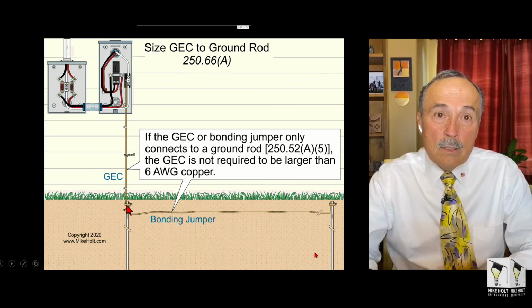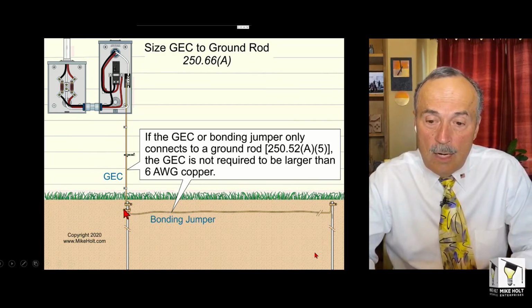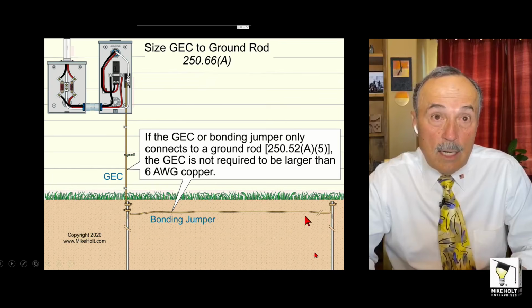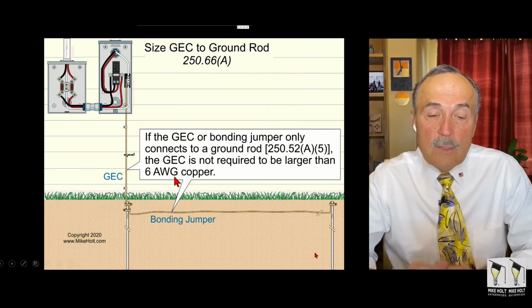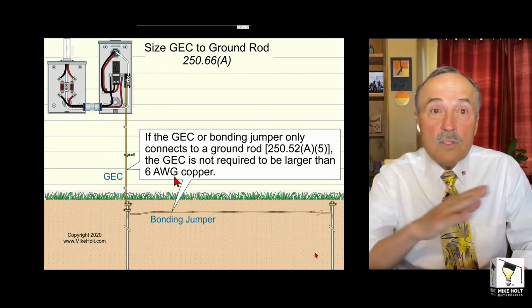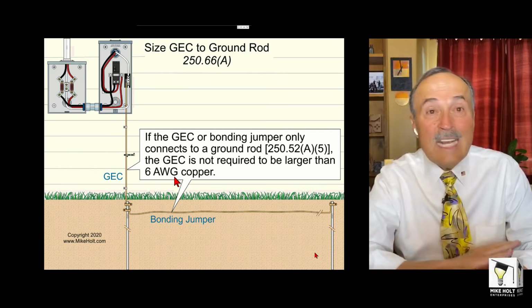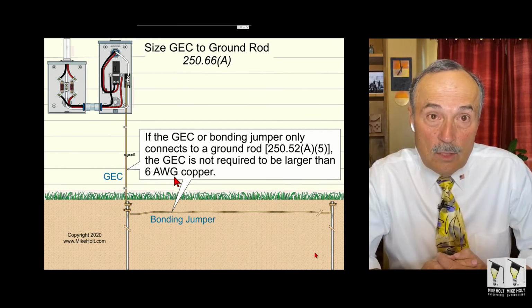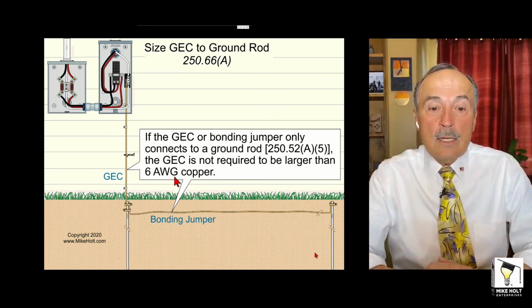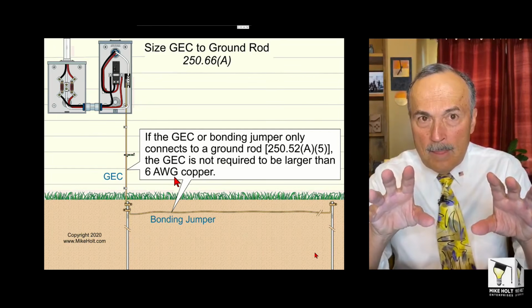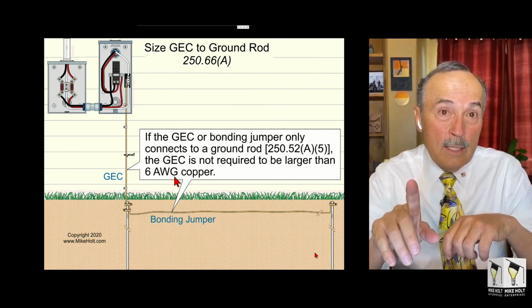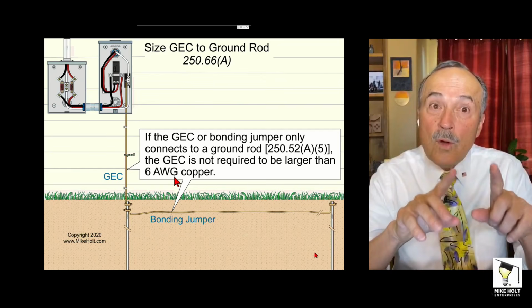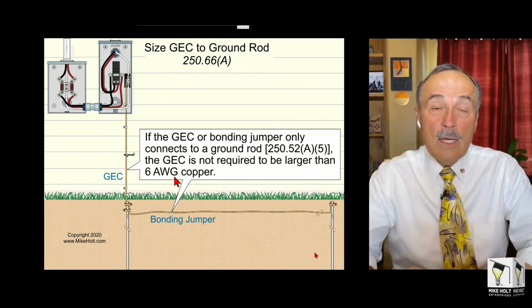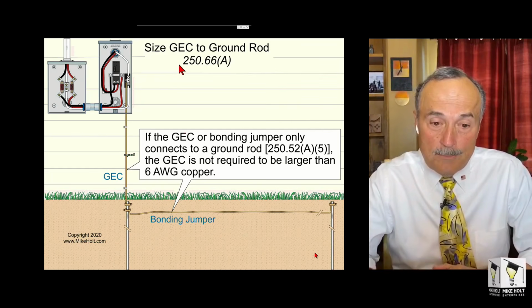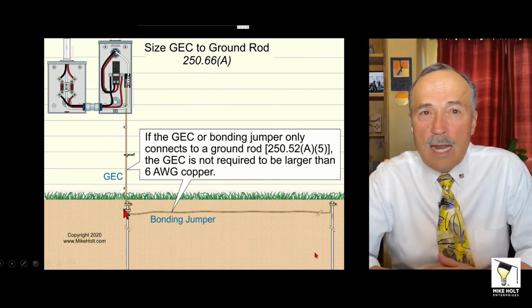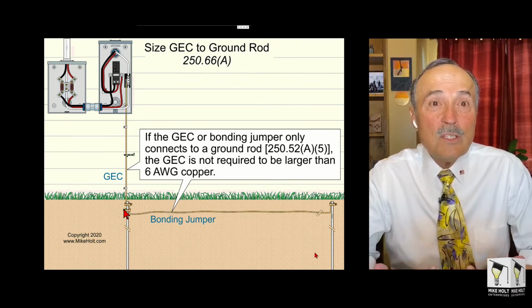You're running a wire to a ground rod, and you're supplementing that ground rod with another electrode, another ground rod, then that wire doesn't have to be larger than 6 gauge. 2,000 amp service, 4,000 amp service, 400 amp service, it doesn't matter. It's not to clear a fault, so we're not trying to size it because of the size of the service. It has to do with system grounding, the purpose in 250.4(A)(1), and it has to do with equipment grounding, 250.4(A)(2), which is a whole other conversation. So what would I always do if I put a couple ground rods for the service? A 6 gauge wire. I don't care if it's a 400 amp, 800 amp, 1200 amp, I don't care because that's what the code tells us.